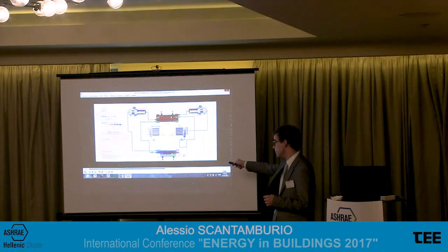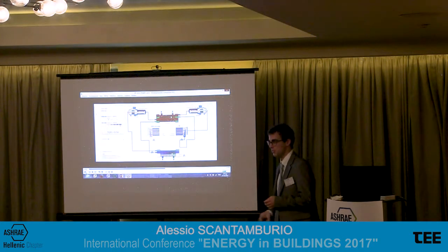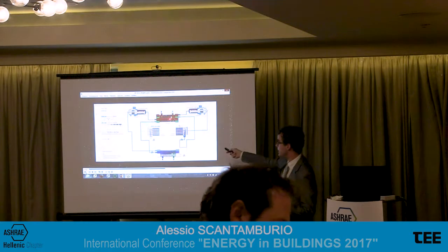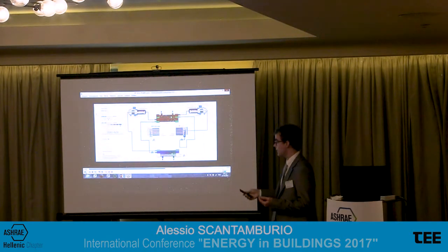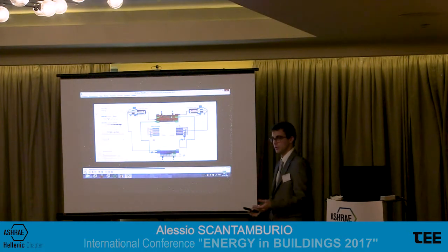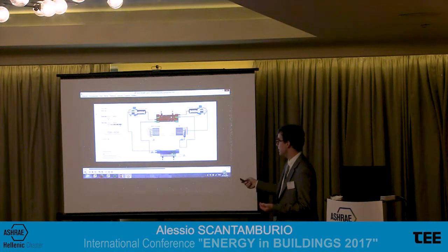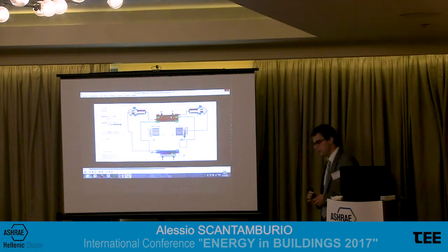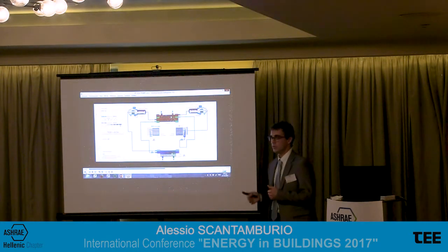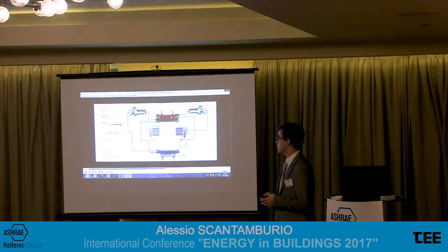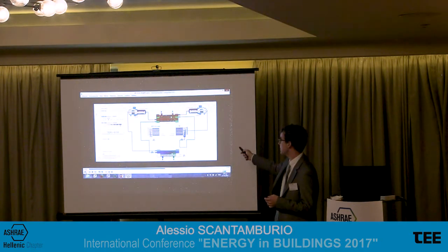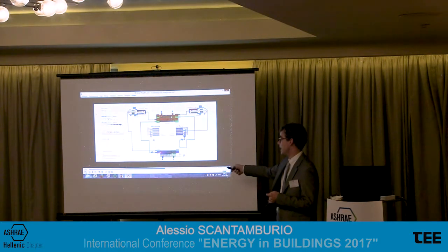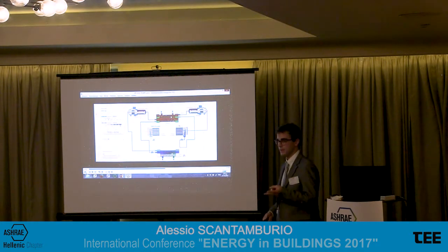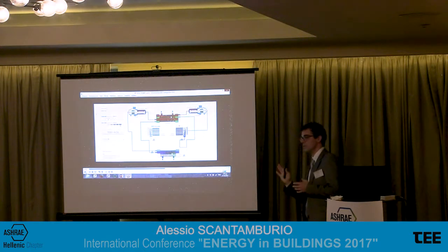So one circuit is using the evaporator to produce cold water, while the other uses the auxiliary exchanger to exchange the remaining energy with the source. In this case, it is an evaporator because the heating load is higher than the cooling load. So I am taking from the source half of the capacity I need at this point here. The real thing about this operating mode is that when the building requires cold water and hot water at the same time, one of the two is for free, because with a single power input of the compressor to produce only hot water, I am producing also cold water, so we have two useful effects at the same time. And this is why the efficiency of this concept is really high.